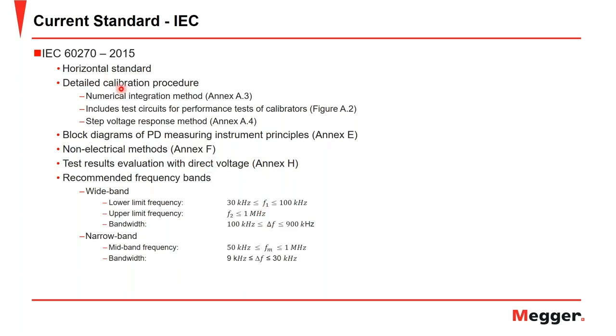So, mentioning the standards that I've talked about plenty of times now, first we're going to talk about the IEC 60270. This is a horizontal standard, which means it's a general standard for all testing, primarily described for laboratory and workshop testing. There are vertical standards that are application-based testing. In this standard, we have a detailed calibration procedure, which we covered earlier. The numerical integration method can be seen in Annex A3, while the step voltage response method can be seen in Annex A4. And you can see some figures of test circuits with their calibrators in figure A2. The standard has block diagrams of partial discharge measurement instrument principles, which we just covered.